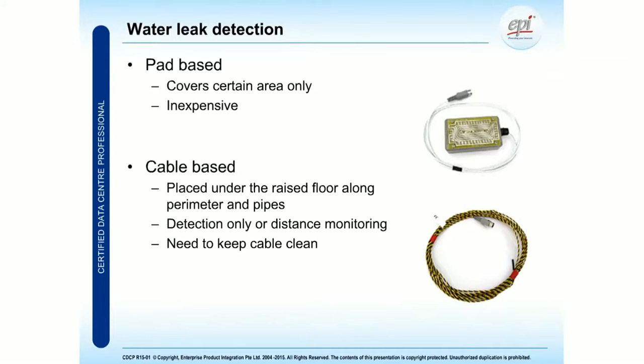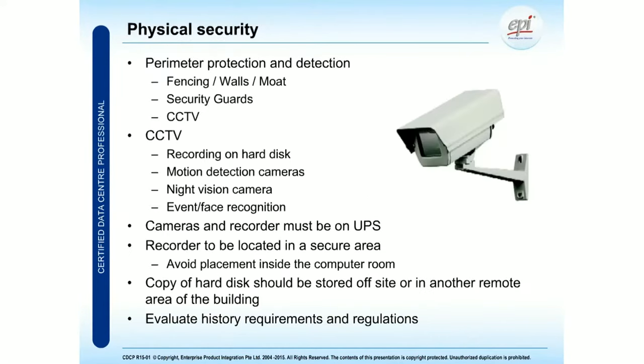But also think about sewage. If restrooms are installed on top of the data center, or if the data center floor is in the basement, there's always a fair risk of water leakage. Also think about outside influences like rainwater coming through the roof or rooftops, where a failing sewage or drainage system could create water leakage inside the data center. We definitely don't want any water near our IT equipment or any powered equipment.